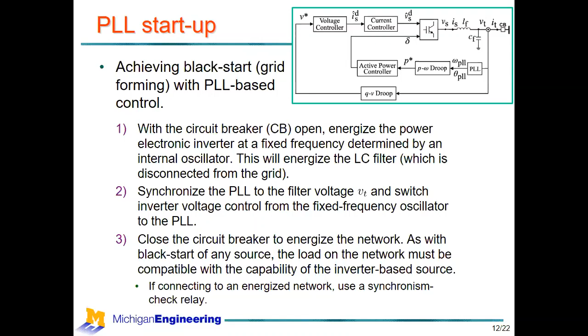If, however, I'm connecting to a grid that's already energized, then there's a slight modification required, which is to use what's called a synchronism or synchro check relay, which says I can only close that circuit breaker when the voltage on either side of it matches. So I can control the phase lock loop to adjust the voltage to achieve the match, close the circuit breaker when there's no voltage drop across it, and I'm then synchronized onto the grid. So the startup process is quite straightforward, and that addresses one of the issues.